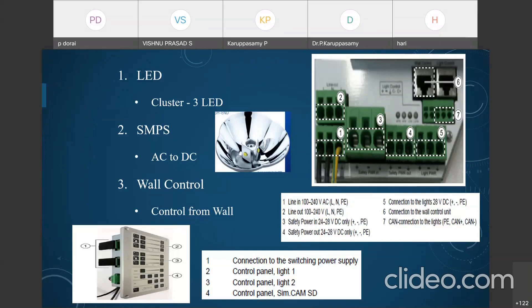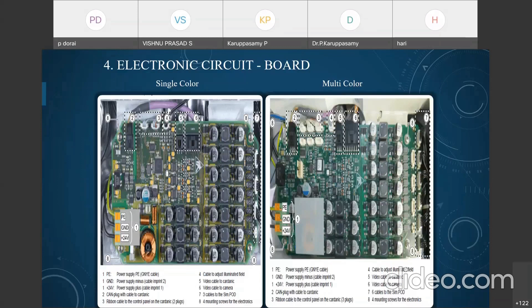This is the main control board, the controller for the entire OT light process. It's incorporated inside the light head, and all individual LEDs connect to it. Depending on the control signal, either increasing or decreasing the diameter, corresponding LEDs will be switched on or off, and the intensity can be increased or decreased simultaneously for all LEDs.